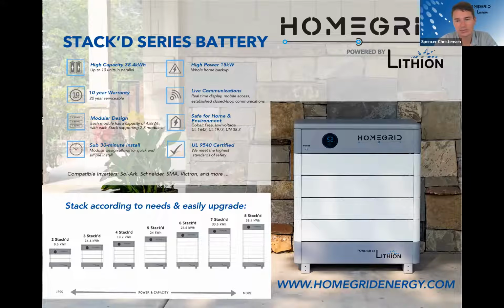What that means for you and your customers is you can power the entire home rather than just fridge and lights. These batteries can do 15 kilowatts continuous with 24 kilowatts surge, matching the Sol-Ark 15K, which also hits those same specs of 15 kilowatts continuous. On the surge for 10 seconds, the battery is 500 amps DC, while the Sol-Ark is 24 kilowatts on the surge.